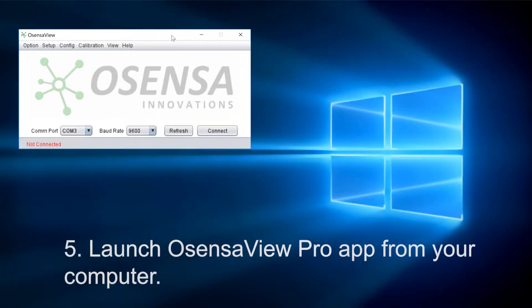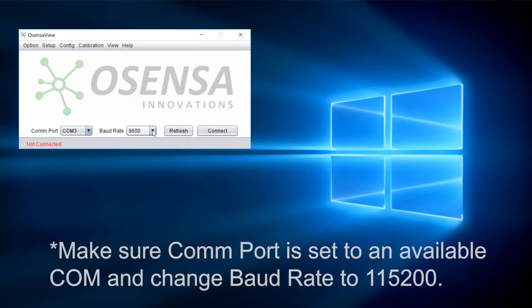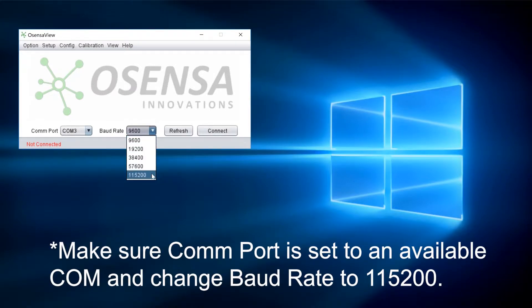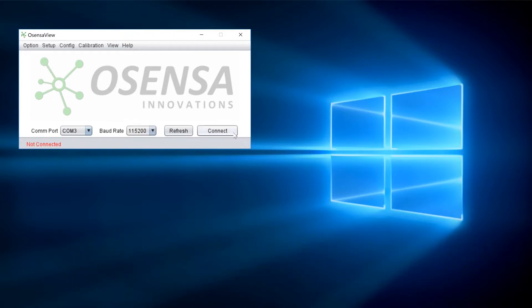Next, launch the OsensaView Pro application from your computer. Once the program is open, make sure the COM port is set to an available COM and change the baud rate to 115200. When you're ready, hit connect.